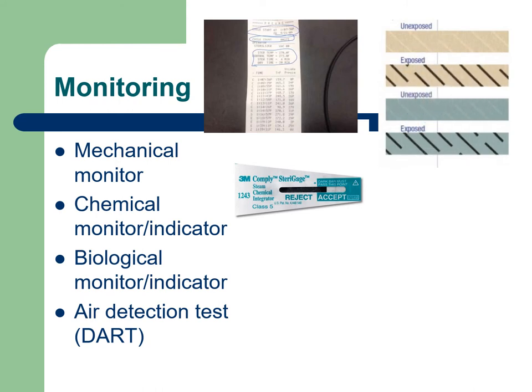Here is some chemical indicator tape. Both of these are steam sterilization tapes. There is also an indicator tape for ethylene oxide, and it is white, and when it is processed, the lines look green. If you're in sterile processing, you want to make sure you get the right tape according to what process you're going to be using, but both of these are steam.